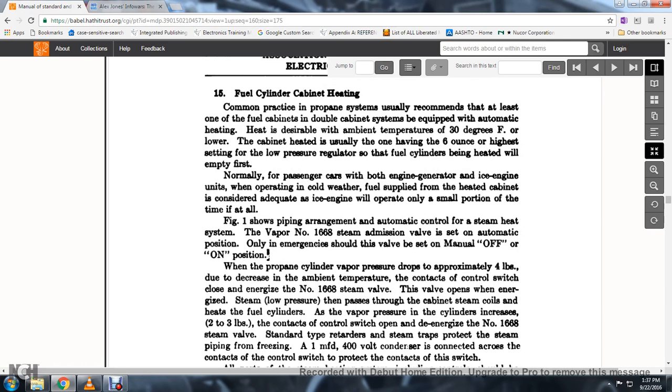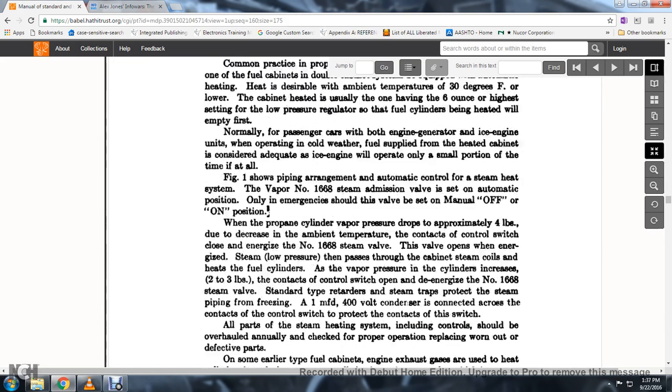So that the fuel cylinder heated is emptied first, normally for passenger cars with both engine and generator ICE engine units operating in cold weather, the fuel supply with the heated cabinet is considered adequate. Figure 1 shows the piping arrangement for automatic control with the steam heat system. The Vapor No. 1668 steam admission valve is set to the automatic position; only in emergency should the valve be set to manual off or on. When the propane cylinder vapor pressure drops to approximately four pounds and the ambient temperature decreases, the contact control switch closes and energizes the No. 1668 steam valve.